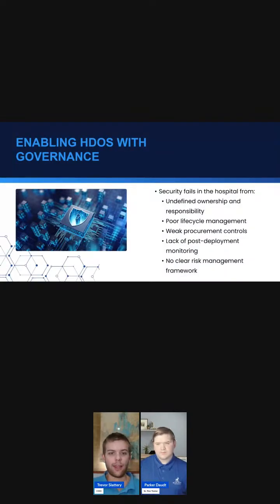Now, one thing that I do like to lean into a little bit here is governance. Governance is where we can have control on a device, on a process, and this is where I think the line is a little bit blurry between the manufacturer and the healthcare delivery organization. We want to see that it is clearly defined who owns and who is responsible for what process. Similarly to how device manufacturers need to properly vet any components they're using in the system, hospitals need to do the same for the device as a whole. They need to follow similar risk management frameworks. They need to follow similar post-deployment monitoring to be sure that the device is secure, even once it has been fielded.